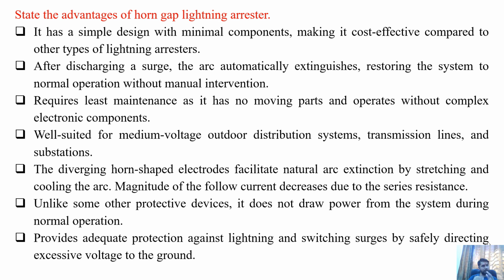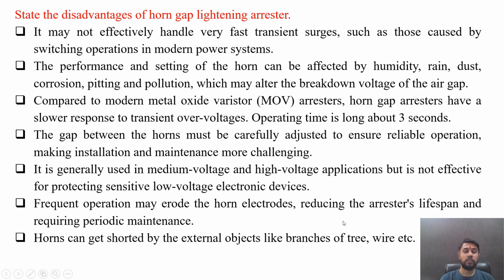The magnitude of the follow current decreases due to the series resistance. Unlike some other protective devices, it does not draw power from the system during its normal operating condition. It provides adequate protection against lightning and switching surges by safely directing the excessive voltage to the ground. So these are some advantages of horn gap lightning arrestor. State the disadvantages of horn gap lightning arresters. So there are several disadvantages of horn gap lightning arrestor compared to other types of arresters. Some are listed over here and we are discussing them in brief.